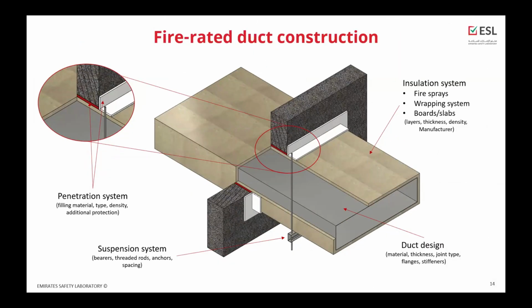So what should be the construction of a good fire-rated duct? Unfortunately, I cannot tell you the details because this is the know-how of each of you, but there are general things which relate to all fire-rated ducts. The duct can be made of steel, or it can be made of boards like calcium silicate type boards, which are also good insulators. So once we have a steel duct and we want to make this steel duct an insulated duct, we need to put an insulation system on it.